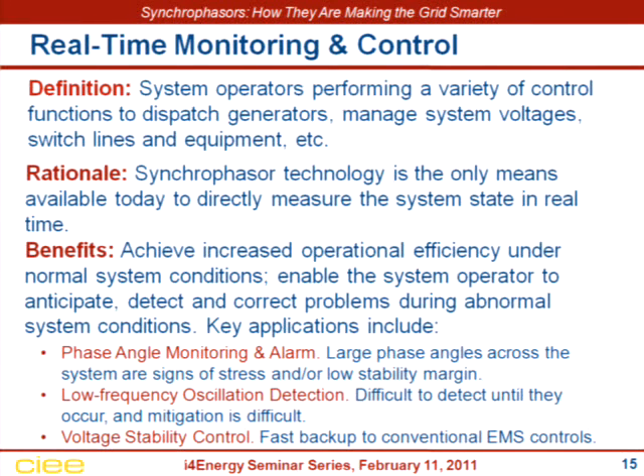We're getting this problem on the Western system now called low-frequency oscillations. This is a new manifestation of something we in the transmission business used to call small signal stability. In other words, the power system starts to oscillate — instead of being steady, the frequency starts to vary, voltages, currents and power flows start to vary, and nobody knows why, and they can't control it. So the only thing operators can do now is back off the power flows, take some of the stress off the system until it calms down. But that's an uneconomic way to operate the power system — it's usually more costly, and you're leaving a lot of unused capacity on the table.